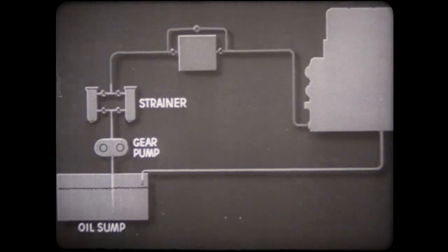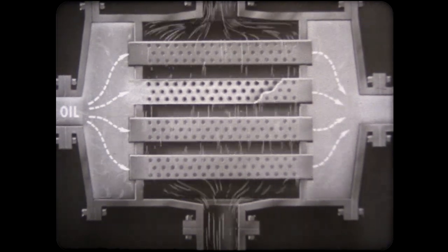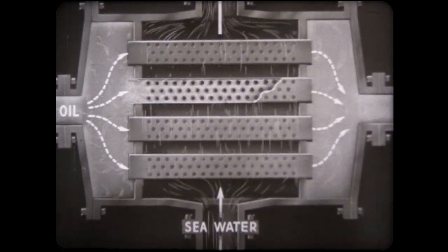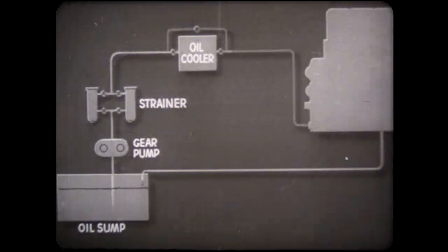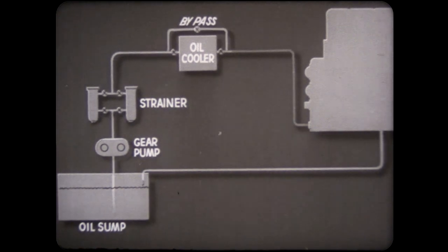The oil next passes through a heat exchanger or cooler, where it is cooled by seawater. Usually the oil flows through a set of tubes around which the seawater circulates. The rate of flow can be regulated to control the rate of cooling. The heat exchanger may be bypassed in cold weather when the oil does not require cooling.